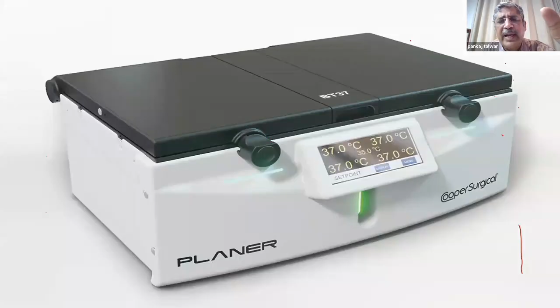So the bigger incubators like this all cost around 16 lakh rupees. Box incubators cost us around 6 lakh rupees. And these small dry gas incubators all cost around 5 to 6 lakh rupees. They've got two chambers here, and they normally give you temperature and humidity. You have a humidification flask put down below. They take dry gas, which is a mixed gas with 6% CO2, 5% O2, and balance nitrogen. It comes with a cylinder from below, and we normally work at 1 bar positive pressure. This is how you can keep 4 patients' plates here on average. But they're actually meant for a single patient. But we can do 4 patients easily in this.